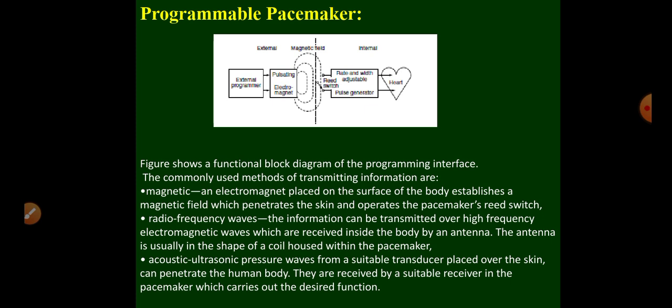An essential requirement of a programmable pacemaker is that it should be immune to accidental programming from naturally occurring energy sources. To meet this requirement, the information is usually coded, and the pacemaker contains a decoding mechanism to recognize proper information. So this programming security code method makes it practically impossible to reprogram an implantable pacemaker through extraneous random magnetic fields.